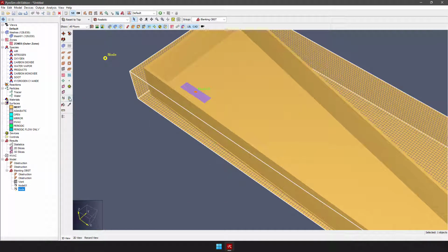Okay, and then I can draw a duct that connects this one to this one. And essentially now this little area becomes like an open vent, because based on the differential of pressure between this node and this node, it will either pull fresh air in or relieve and flow air out through this node. It's kind of like an opening on the floor right here.